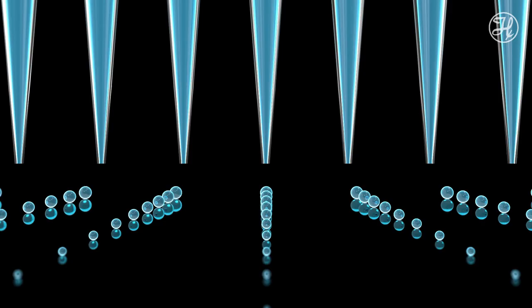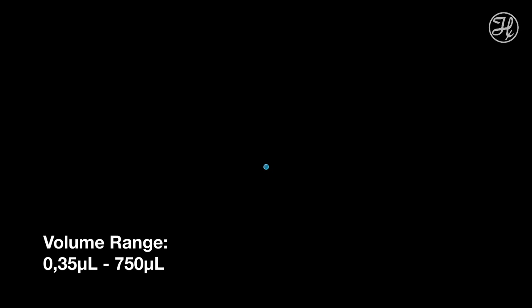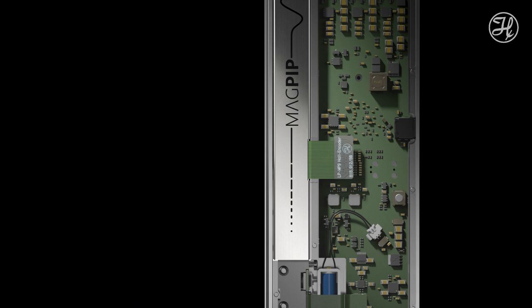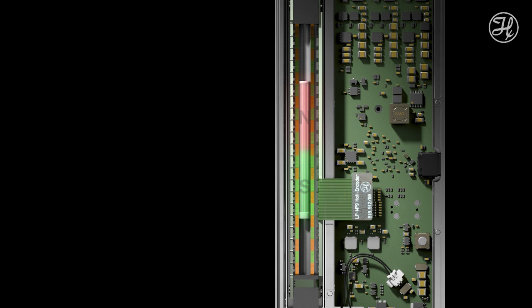Larger volumes of up to 750 µL can be pipetted in the conventional air displacement pipetting mode. The key technology used in the MagPIP is the tubular linear motor. Using the moving part of this motor as a plunger for the pipetting enables unprecedented acceleration and allows for even the smallest amounts of liquid to be pipetted.